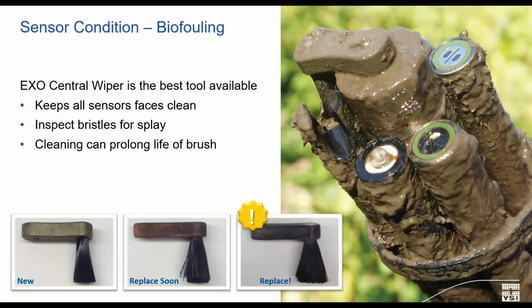One of the most obvious things to visually inspect is the wiper block assembly. Over time, the bristles on the wiper brush will become splayed and lose the ability to keep the sensor faces clean. If your brush looks like the photo on the right, it is time to install a new brush. To help prolong the life of these brushes, after each deployment, the brush should be cleaned out under running water using a toothbrush to clean the debris from the bristles, and then place a bread tie around the bristles to allow them to dry back in their original shape.